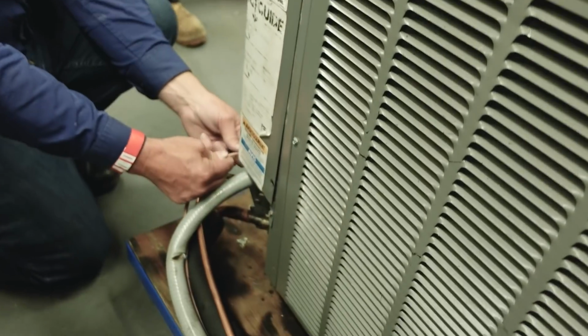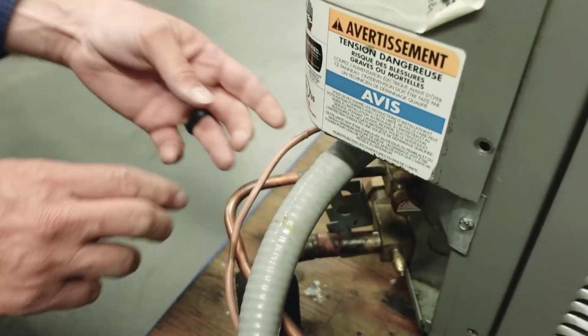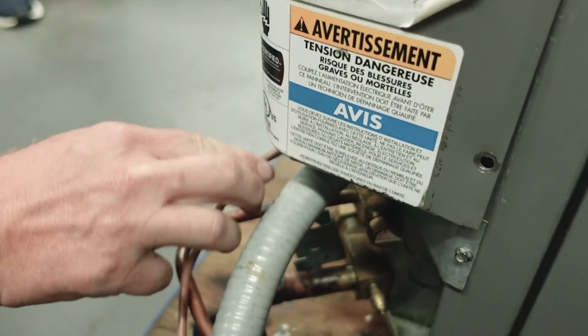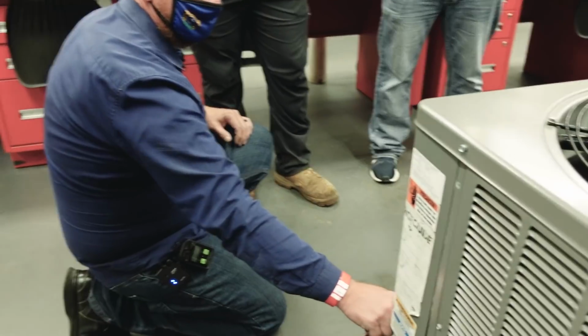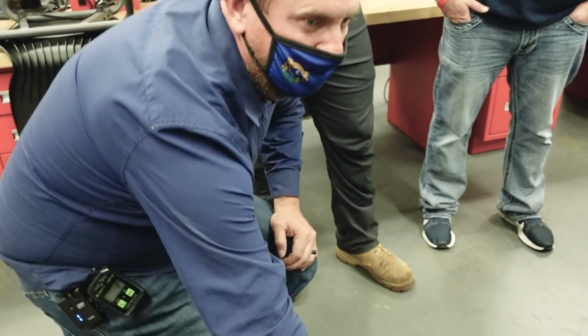If you're looking for a short, you're going to check those low voltage wires inside the unit and outside the unit. Notice how these wires are exposed. Look how somebody burned it, that's a prime example. Somebody used a grommet right here to make sure it doesn't rub, but I've seen tons of times where this wire rubs into the metal. Let's see where it goes on the other side.